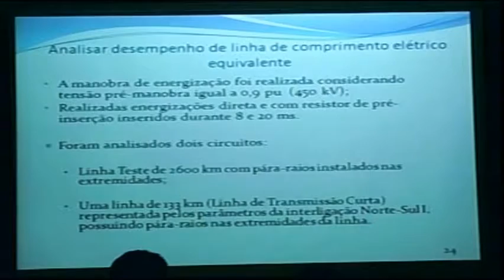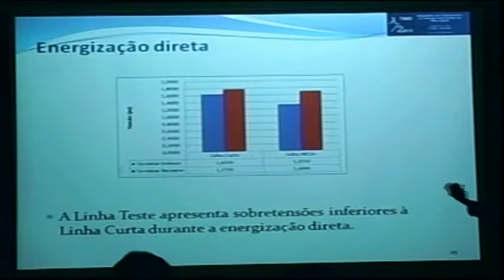In this case, 2,600 kilometers with the surge arrestor installed on the terminal substations, and this one only on the terminal substation. So here the voltage on the sending end, on the short line, is 1.70 pu, here 1.60, so the half wavelength is compensating. It should get the same value, but since you damp it more, since the traveling wave goes further, you get smaller overvoltages.